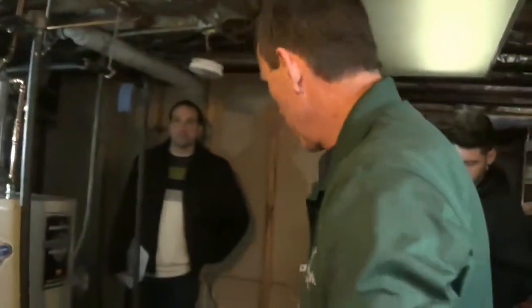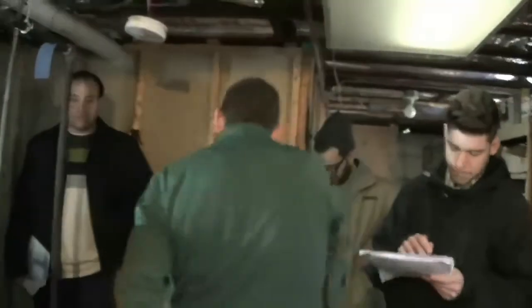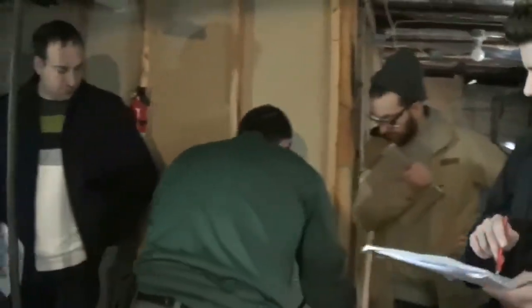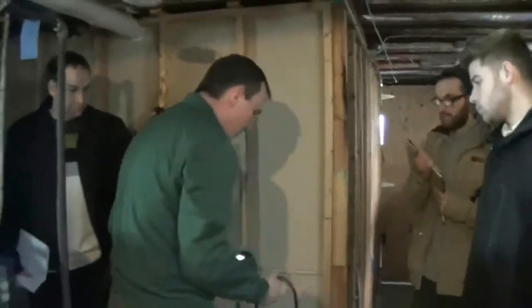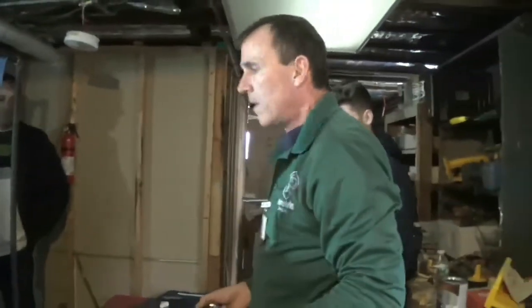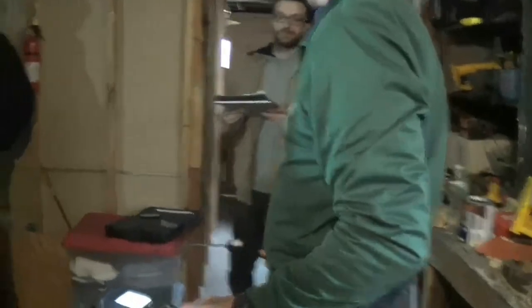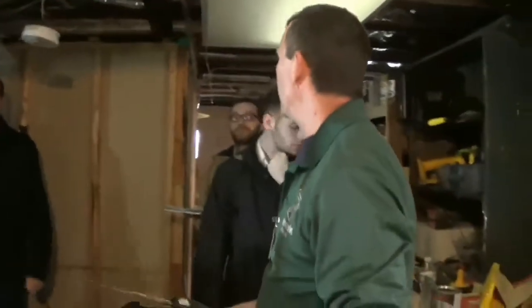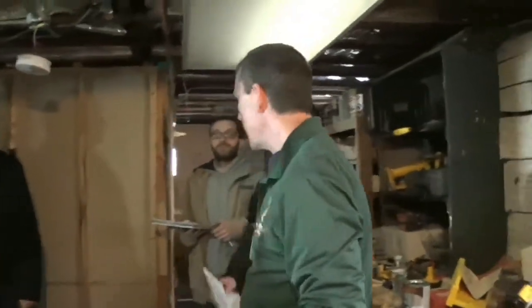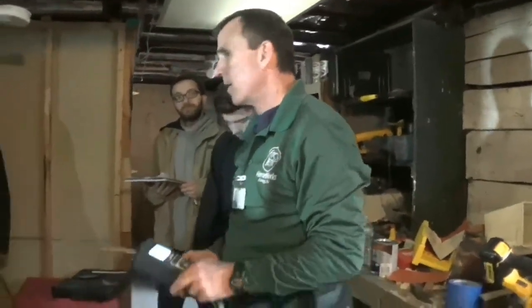Now, while we're doing all this testing, we have these combustion appliances going. Yep. Should we be paying attention to our ambient CO? Absolutely, and that's why I've had this thing running over here. In the combustion appliance zone is where you're going to get some ambient CO after the appliances have been on, right? And especially if they're spilling. Yeah. I've been here before, and there's enough of a draft that it's not building up in here. So you're not getting much ambient in this area.